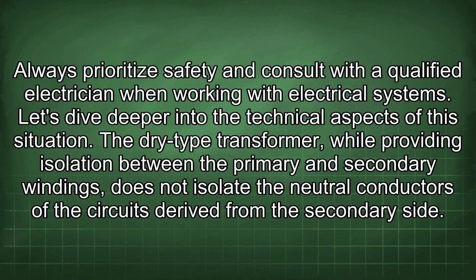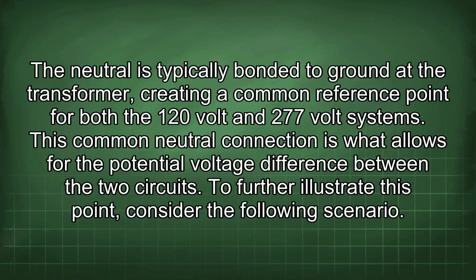Let's dive deeper into the technical aspects of this situation. The dry-type transformer, while providing isolation between the primary and secondary windings, does not isolate the neutral conductors of the circuits derived from the secondary side. The neutral is typically bonded to ground at the transformer, creating a common reference point for both the 120-volt and 277-volt system. This common neutral connection is what allows for the potential voltage difference between the two circuits.